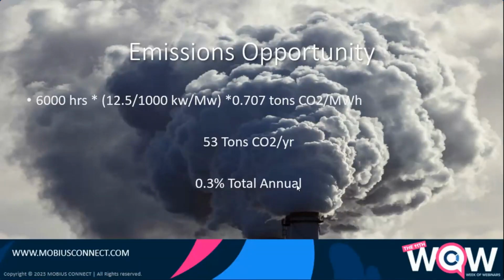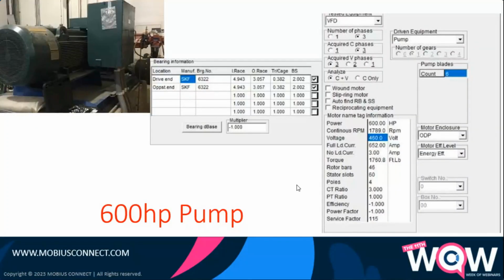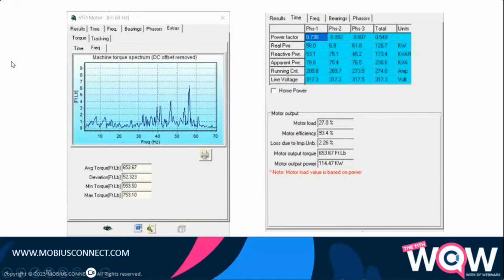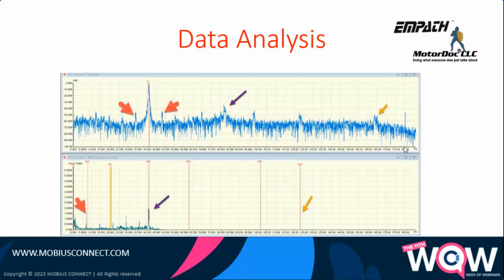Now we'll take a look. This is not the same location. This is a 600 horsepower machine. These are the bearings. They had two 6322s on this machine here. This is actually an alignment issue. So 600 horsepower, taking a look at it, lightly loaded. We're talking about 126 kilowatts input, 114 output, giving me 93.4% efficiency, which is really low, but they're at 27% load. We took the measurement.